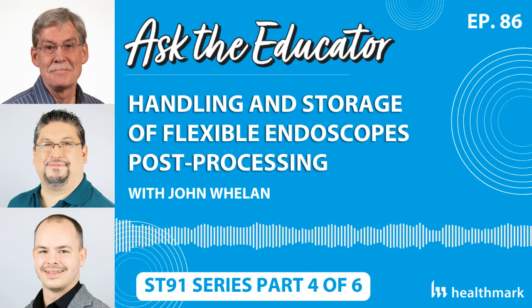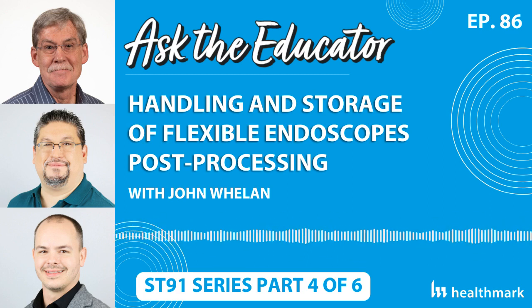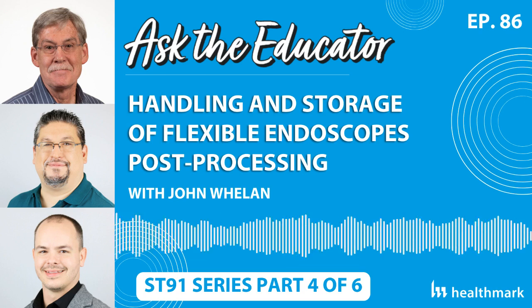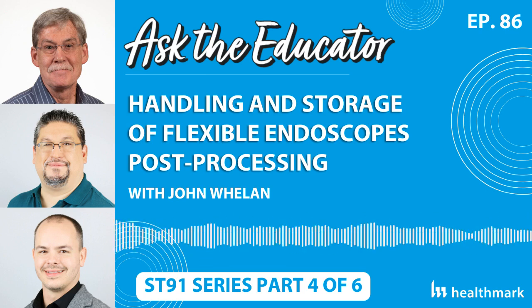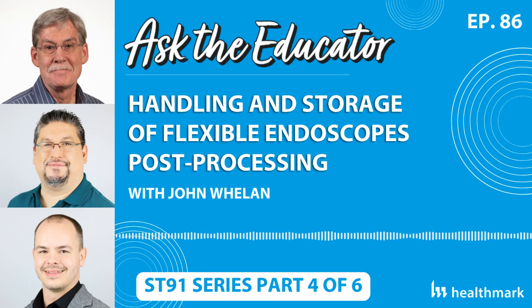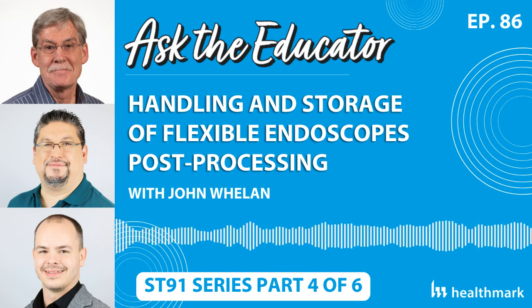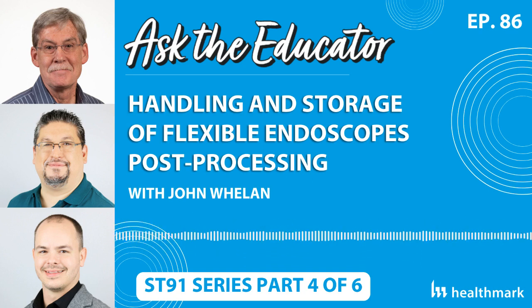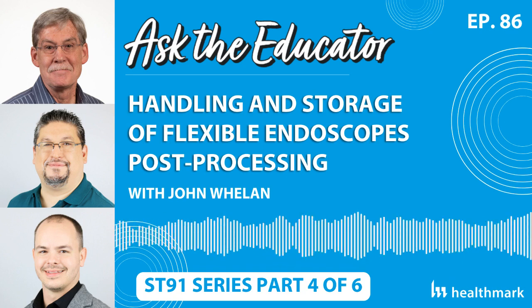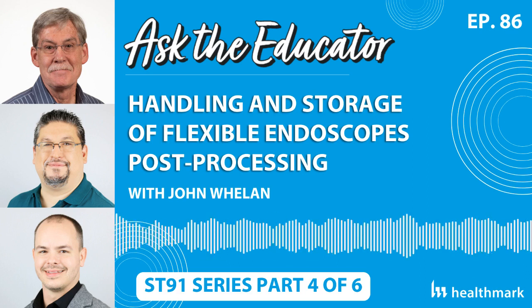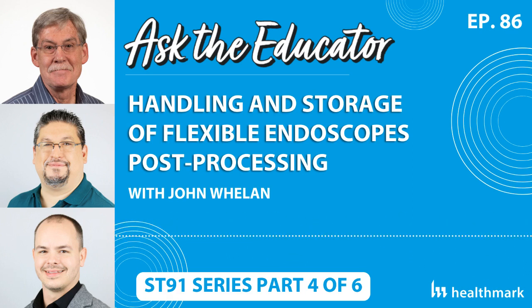Yep. So that's a very good question, and I run into that a lot too. What ST91 says is drying cabinets are preferred, but minimally, cabinets with filtered air blowing into them are acceptable. So it doesn't mean everybody's got to run out and buy very expensive drying cabinets. If you have the opportunity to do that, think of a standard being updated or replaced that's based on best practice and on clinical investigations and research as your opportunity to have the ammunition, if you will, that you need to seek funding as you're able to get to the next level. The term standard refers to achieving a certain level of performance, and that's what this is about.